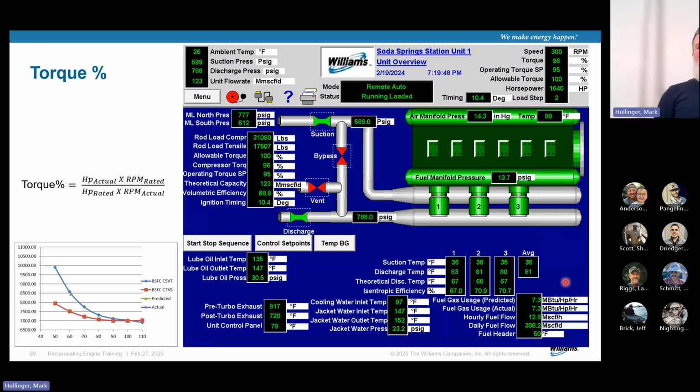fuel in, compressor compressed, so throughput compressed, right? So it's just generating horsepower, and here's how much fuel it took you. Maybe that's an easier way of putting that, okay? So this is a performance parameter, and it's predicted off some curves that we put into the PLC. Most of them are correct. There's a couple that might be slightly off. And then we alarm off it, so it might be annoying.